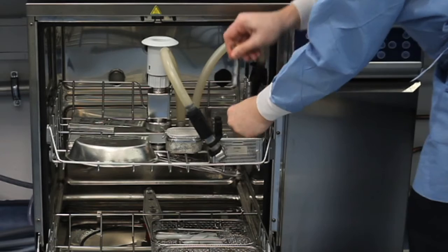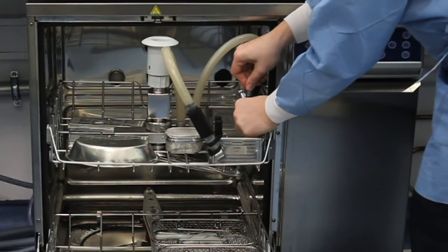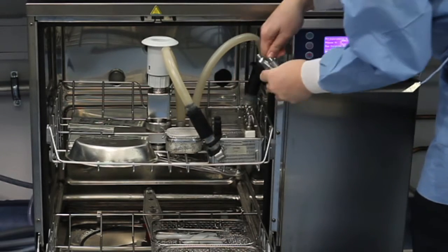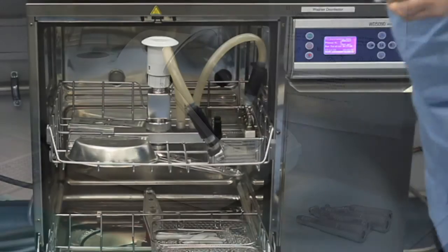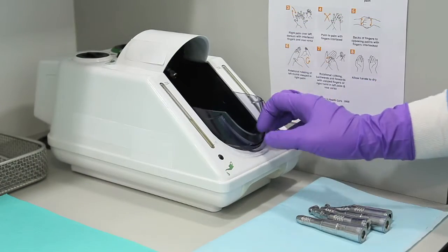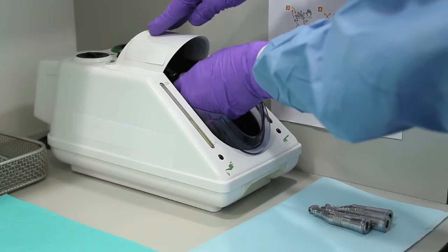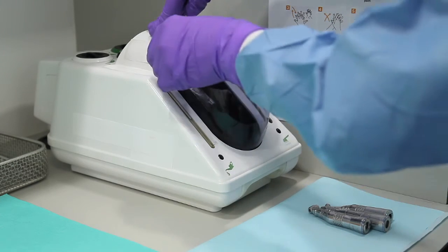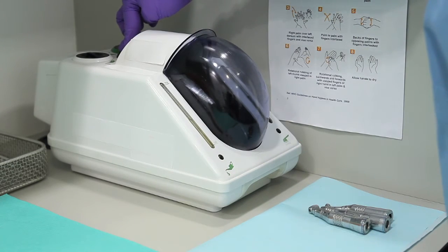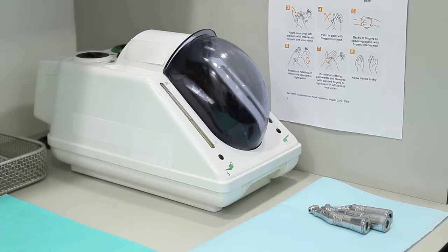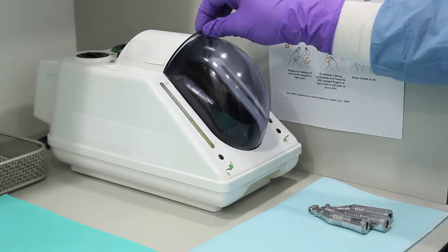When dental handpieces are removed from the washer disinfector, they need to be lubricated. The dental handpiece maintenance system is a machine which propels an oil-based lubricant under pressure into dental handpieces. Lubrication is essential to ensure handpieces function correctly. Only use a lubricant recommended by the dental handpiece manufacturer.